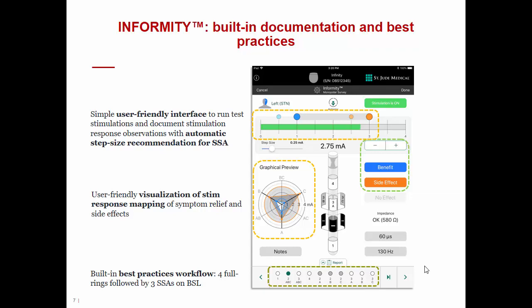The critical point of programming through Informity is testing and reporting on this bar when benefits occur. We can mark partial benefits as well as complete benefits, displayed as a dash and lighter blue versus a full blue color. Going up, we can also display partial or transient side effects in pale orange versus persistent side effects in full orange. Importantly, as soon as we click the side effect button, Informity automatically reduces the stimulation intensity by one step size so the patient does not experience side effects while we document them.